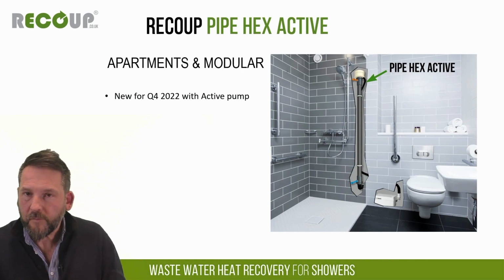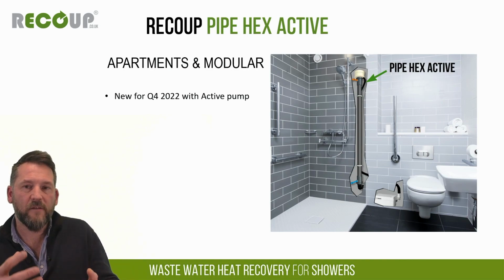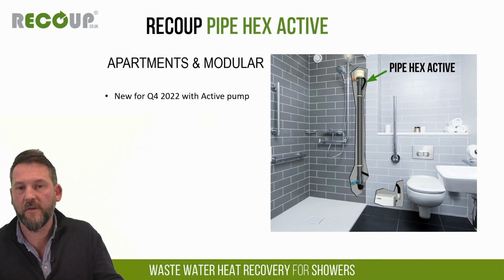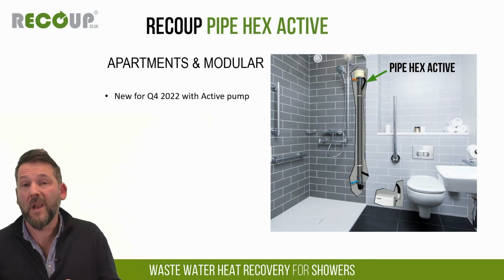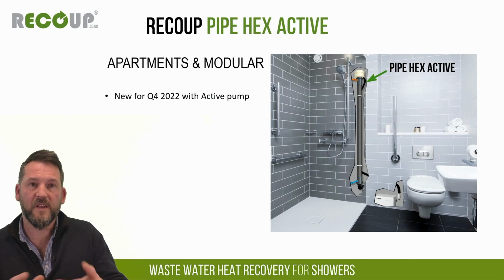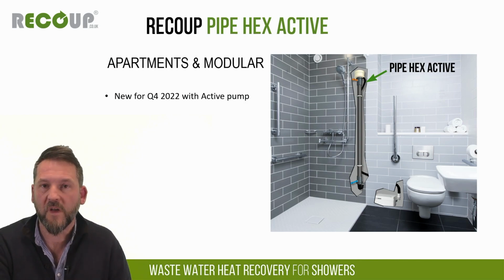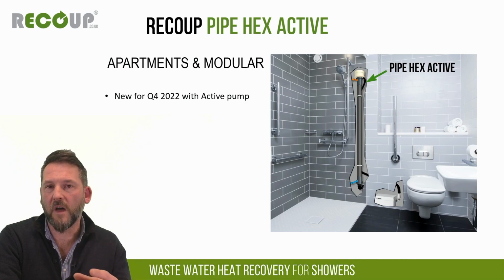The way the pump works is it's already a very low wattage pump, around about 250 watts. But the way the system's designed with the buffer tank at the top, it's designed so that the pump is only in use for about 1/3 of the time that the shower is operating. So it means overall we get a very, very low additional electrical requirement for the wastewater heat recovery system. So low, in fact, that in the SAP PCDB database listing, they haven't attributed any energy loss from the pump system. So it really is still a very high scoring SAP option, this one.